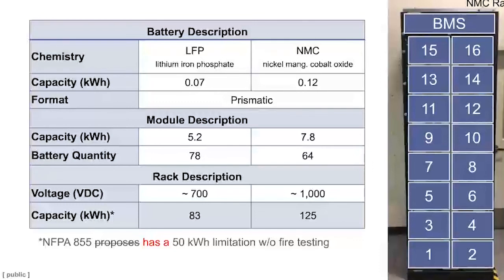Now, I'm assuming that these systems are running under an abuse condition. So the BMS is not active. There's no active electronic protection for these systems. Because I'm trying to evaluate the hazard of my combustible, we're going to take a reasonable step to ignite the combustible, and then we want to see how the protection system performs. So in this case, the BMS system is essentially just a solid metal box at the top of the rack.